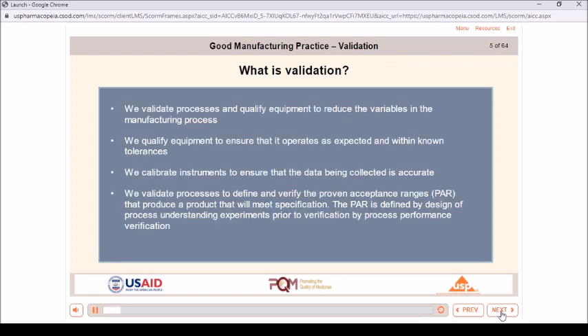What is validation? We validate processes and qualify equipment to reduce the variables in the manufacturing process. We qualify equipment to ensure that it operates as expected and within known tolerances. We calibrate instruments to ensure that the data being collected is accurate. We validate processes to define and verify the proven acceptance ranges, PAR, that produce a product that will meet specification. The PAR is defined by design of process understanding experiments prior to verification by process performance verification.